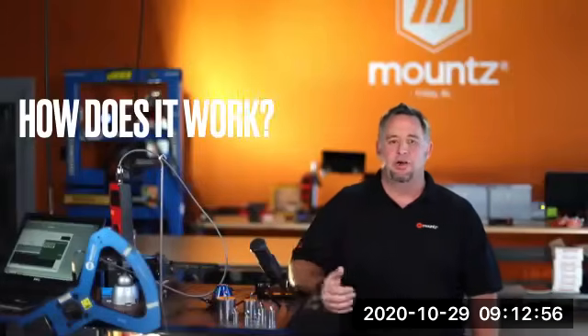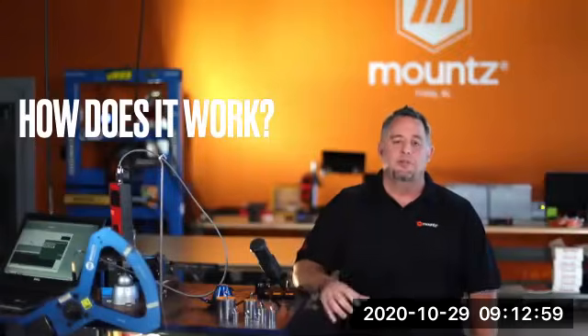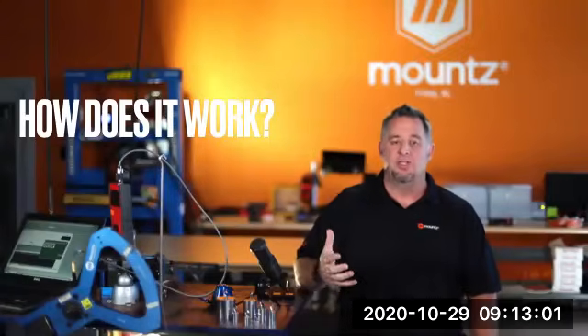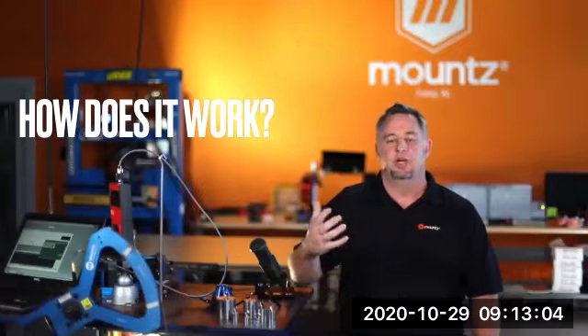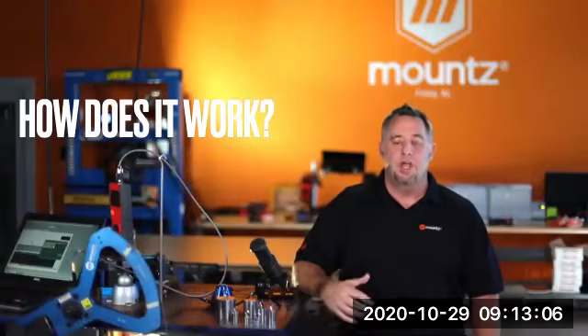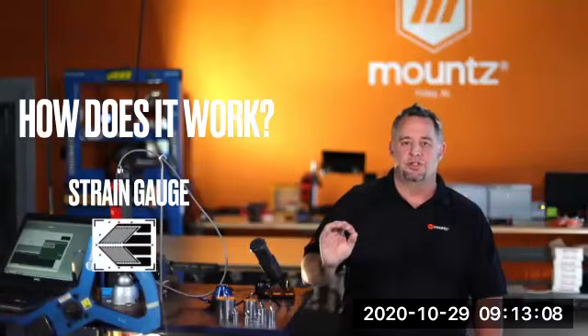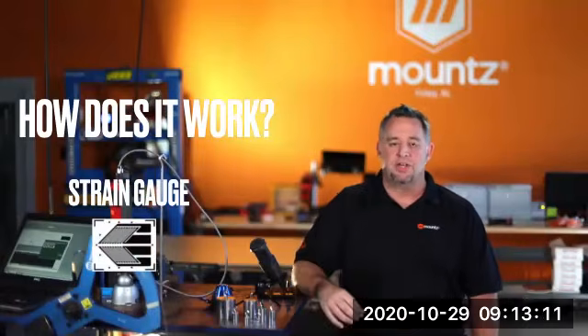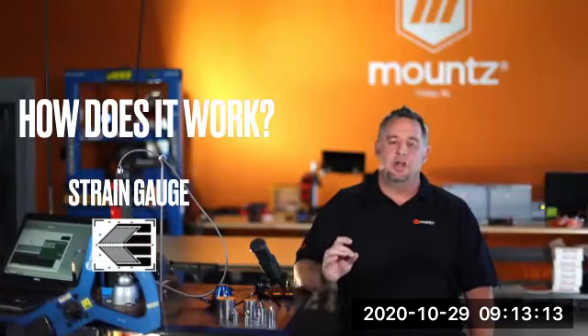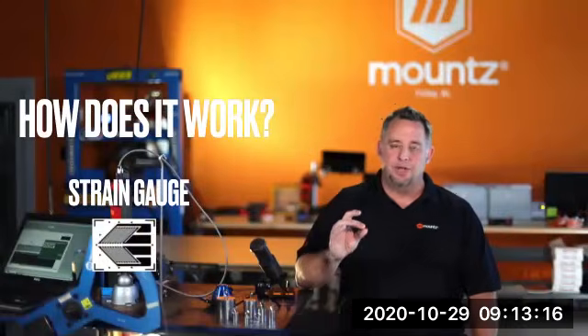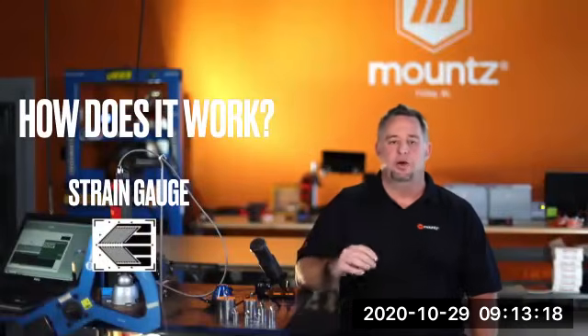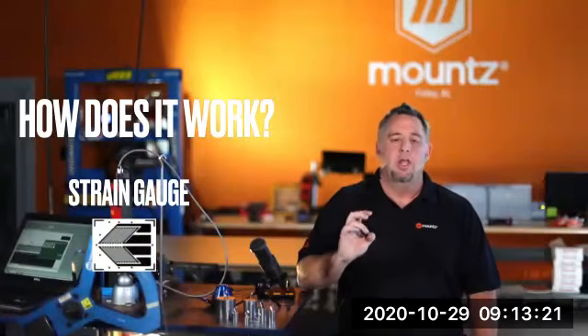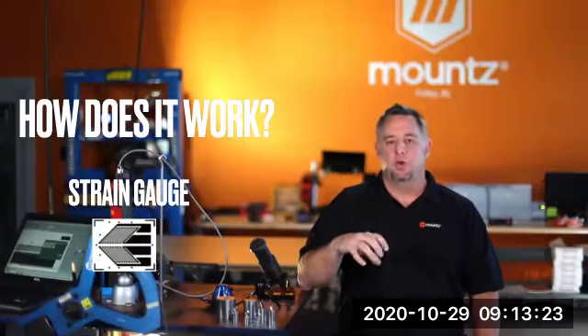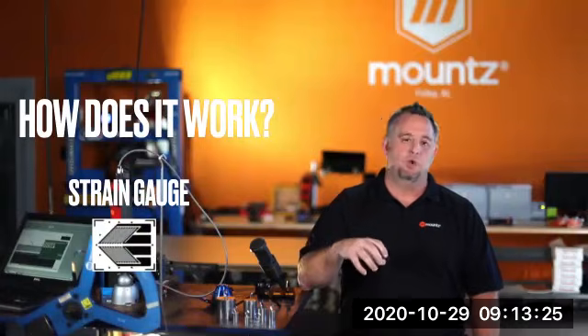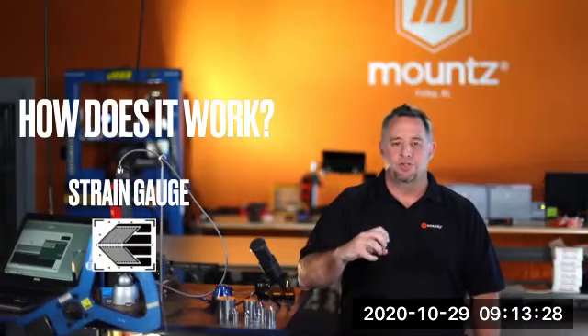So in essence, how does this entire thing work? First we have the analyzer itself. It is married to a sensor that we're using, and it all starts with a strain gauge for our reaction style transducer. The strain gauge is a very small electrified circuit that is laminated onto either a rod or a bar. And as we apply torque to that rod or bar, we do see torsional forces that happen.